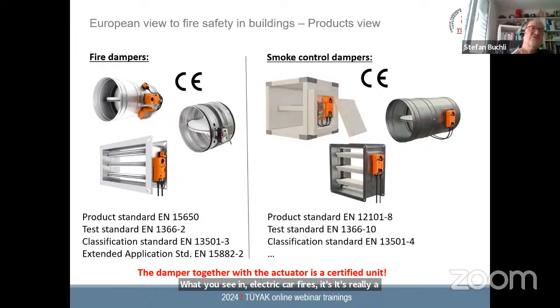The fire starts very rapidly. It's not an explosion, but it's almost an explosion. The energy peak goes up quite high, very fast, but then it goes down again quite soon. The fire of a standard gas car goes up a little bit slower, and then it goes down also slower. So from the energy point of view, there is not a big difference. I think it will not have a big impact on the fire damper specification, classification, or the smoke control system.